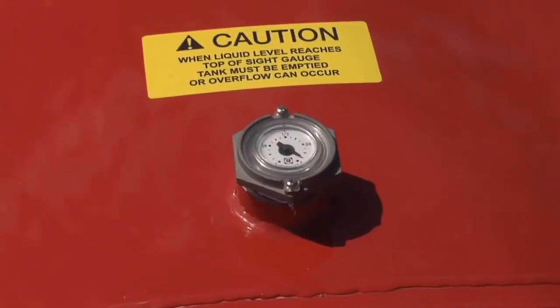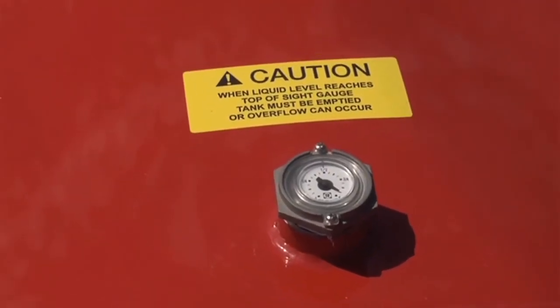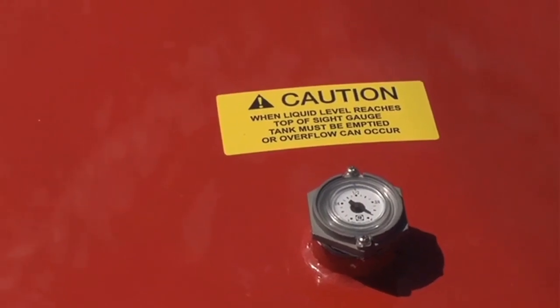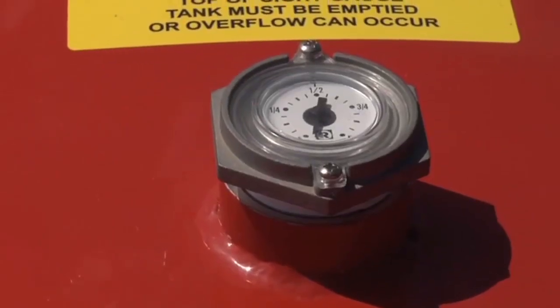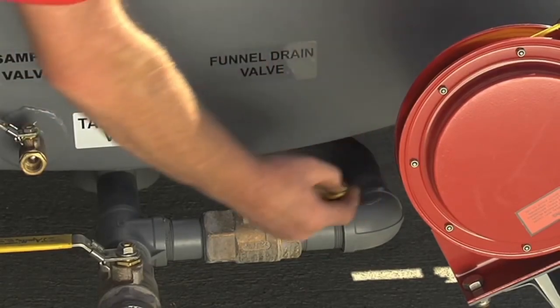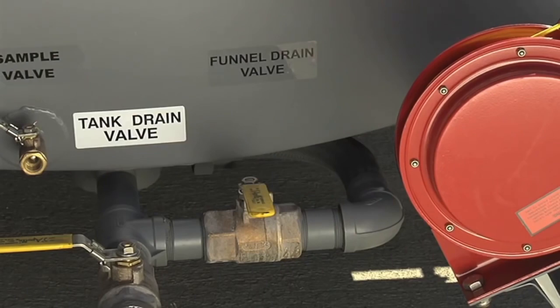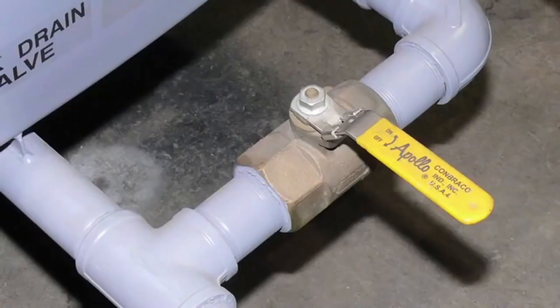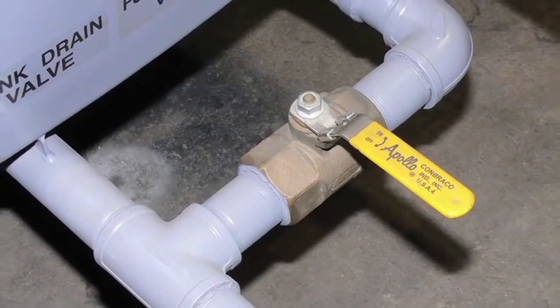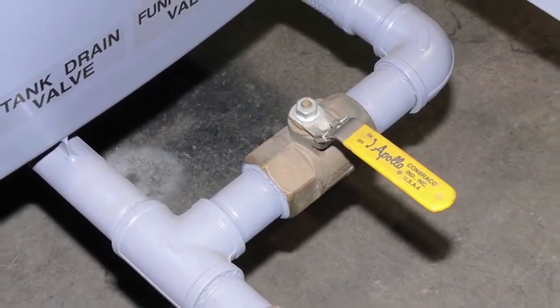On top of the tank, check the liquid level gauge. The SealVac will shut off before filling completely, but it is good practice to start the job with an empty tank. In the rear of the tank, we see a main drain valve and a funnel isolation valve. These should both be closed for vacuum operation. The valves are closed when rotated 90 degrees relative to the plumbing.